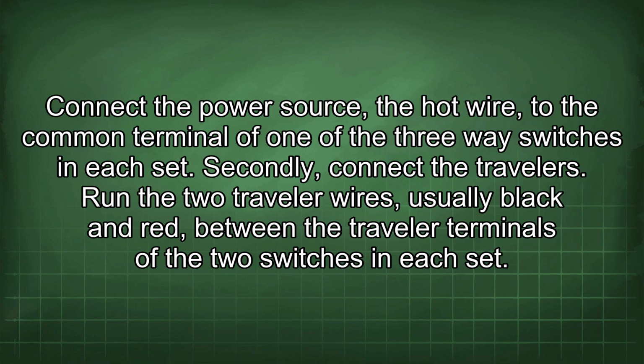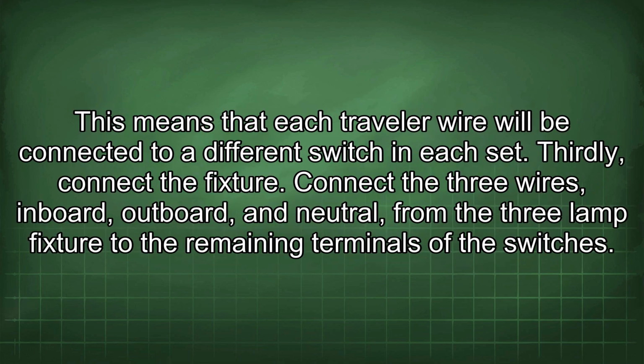Secondly, connect the travelers. Run the two traveler wires, usually black and red, between the traveler terminals of the two switches in each set. This means that each traveler wire will be connected to a different switch in each set.